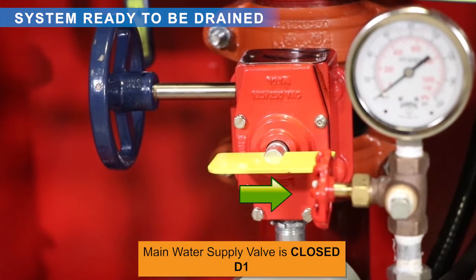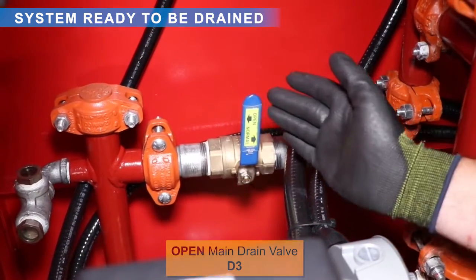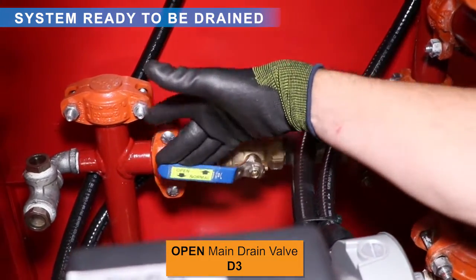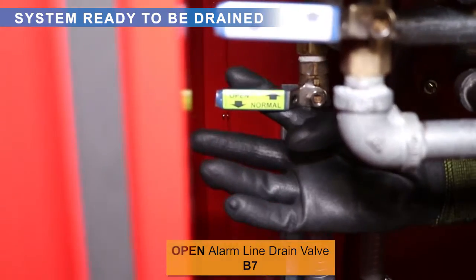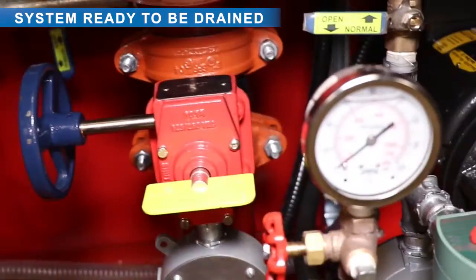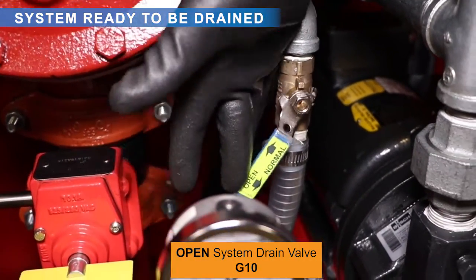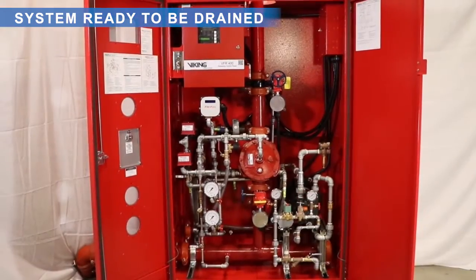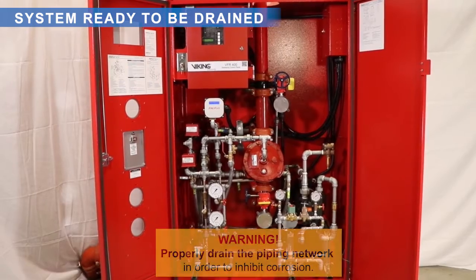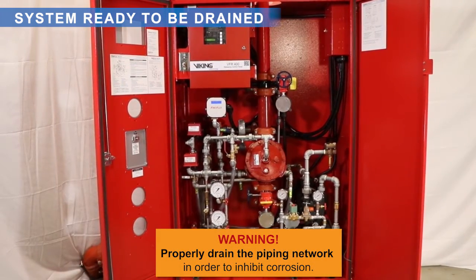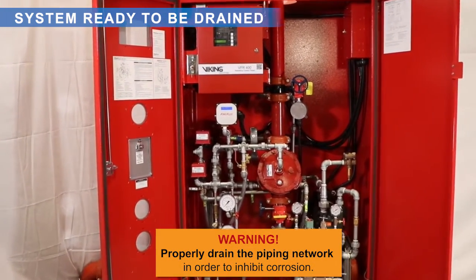Verify that main water supply valve is closed. Open main drain valve, alarm line drain valve, and system drain valve to completely drain the vacuum sprinkler piping. Wait a few minutes to ensure the system is completely drained. It is very important to properly drain the piping network in order to inhibit corrosion.